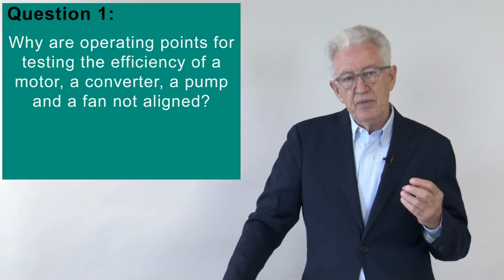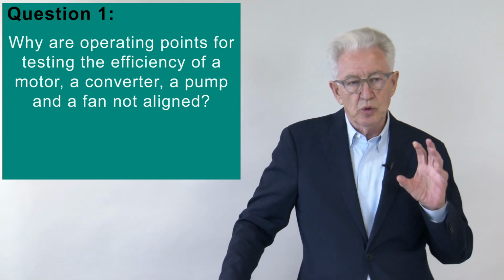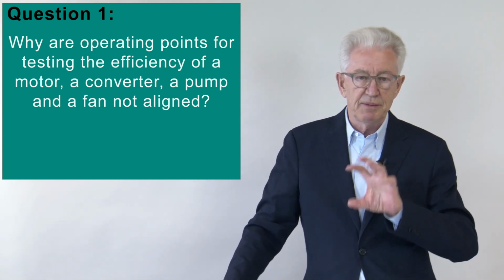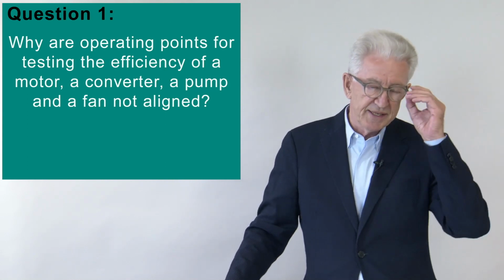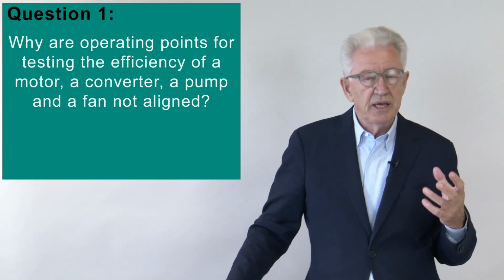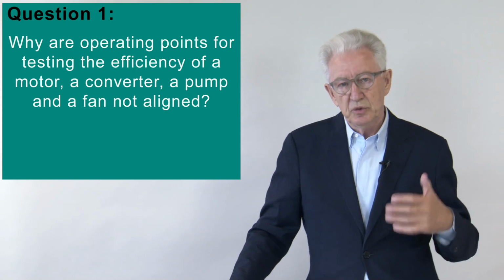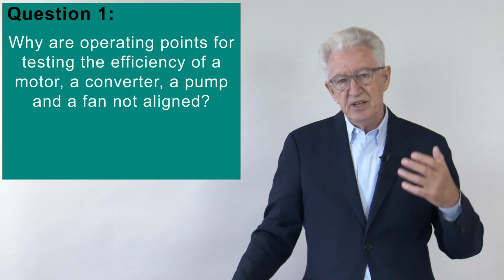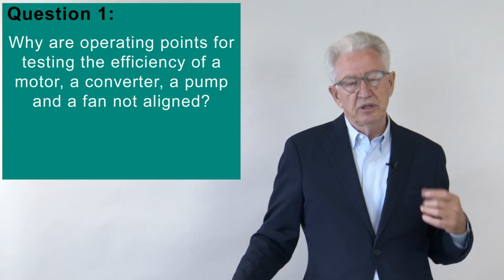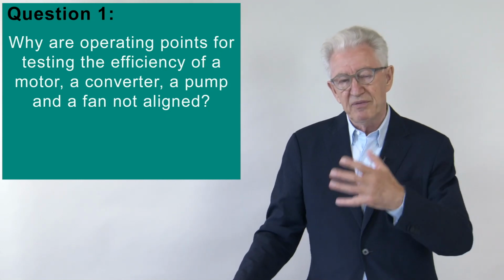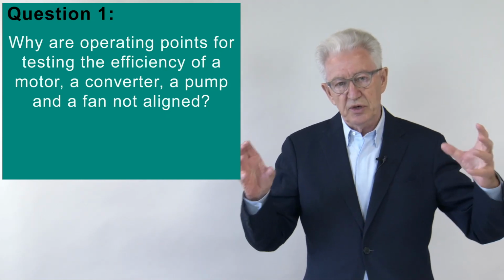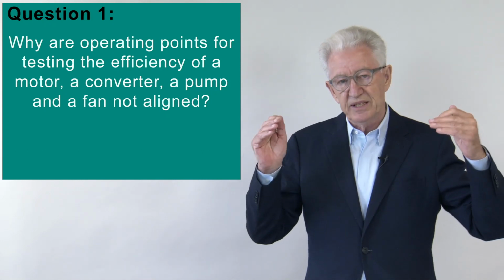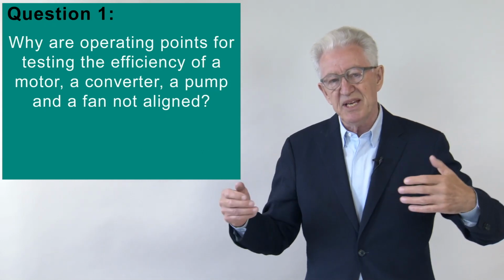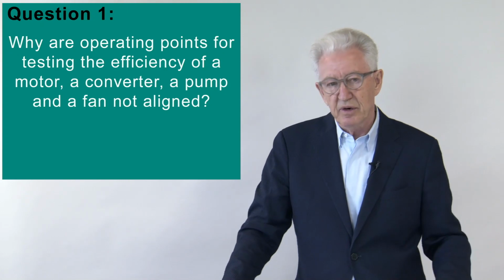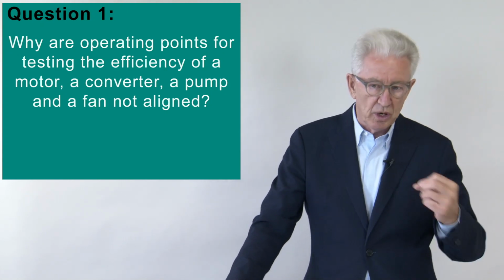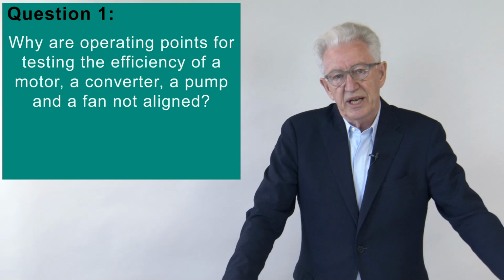When we talk about electric motor-driven systems, the coordination between all the major elements has to be well organized. And one of the elements of the coordination is to test the efficiency. To test the efficiency, the motor manufacturer, the VFD manufacturer, and the pump manufacturer have to agree on a certain point, their load, their torque, and their speed, or in the case of a pump, their head and their flow, that is tested. They have to be coordinated.